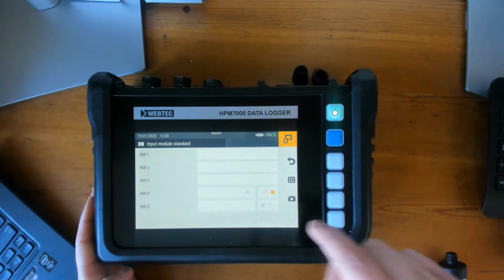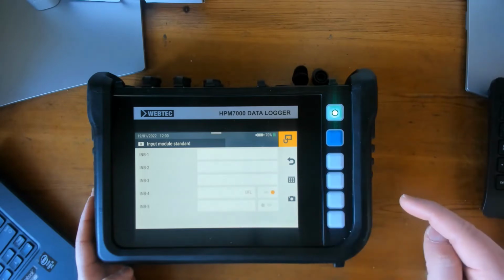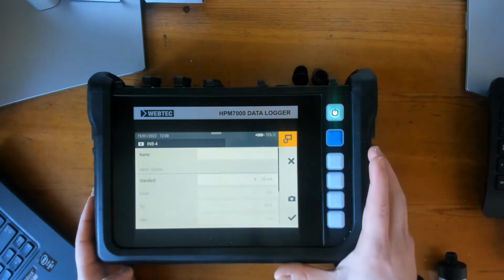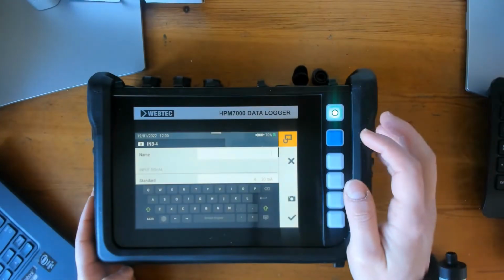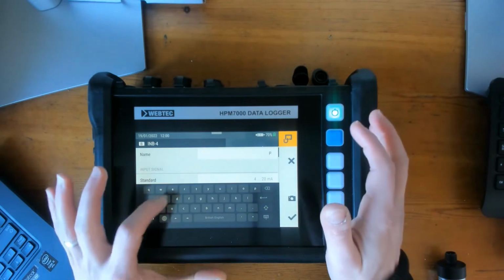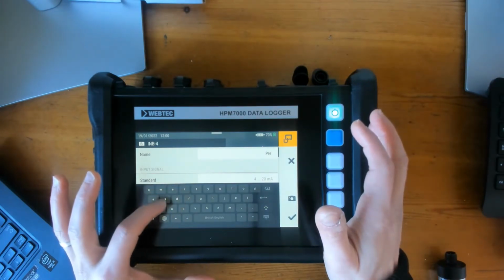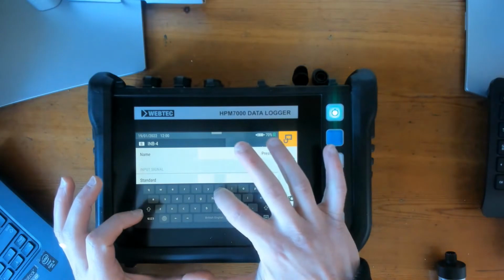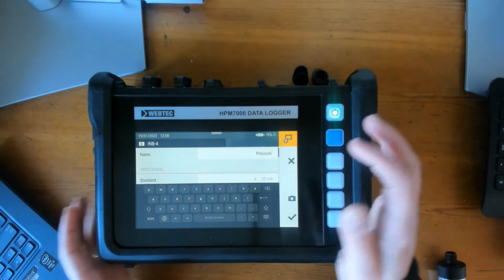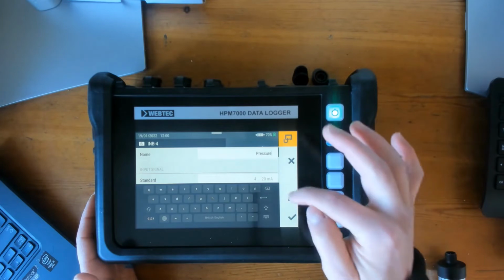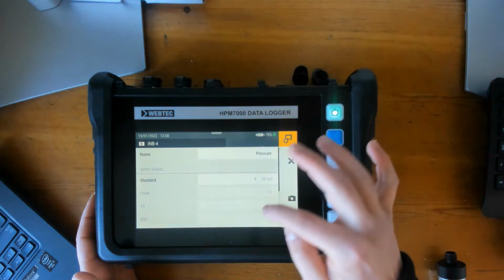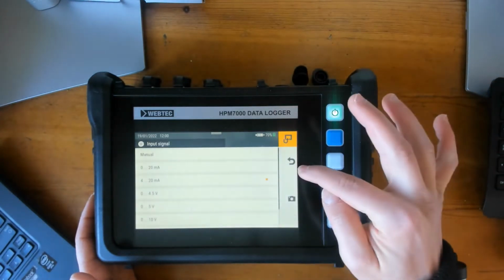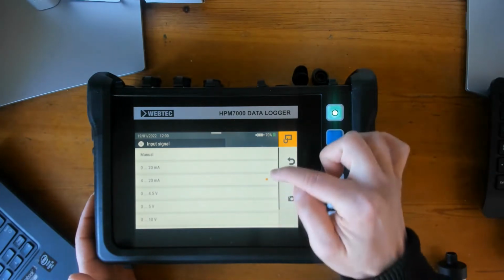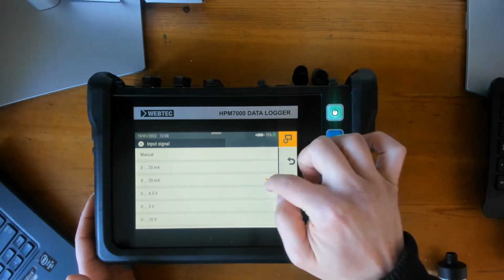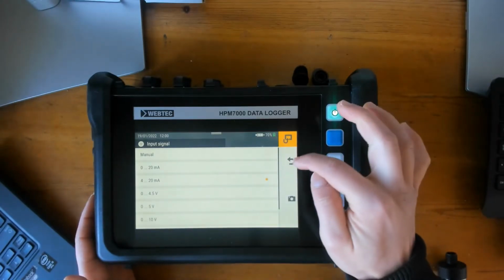So we switch it on and we tap in here. We can give it a name. Let's call it pressure. Here you will select which type of sensor you will be using. So in this case, we will be using a 4 to 20 milliamp sensor, so we will leave it there.